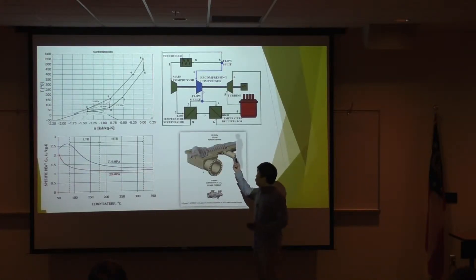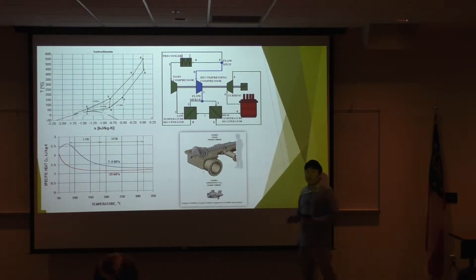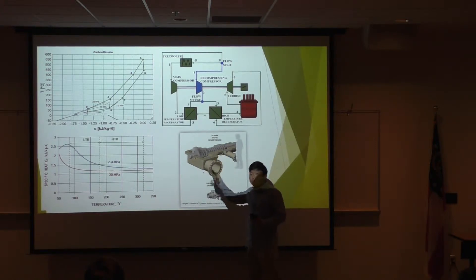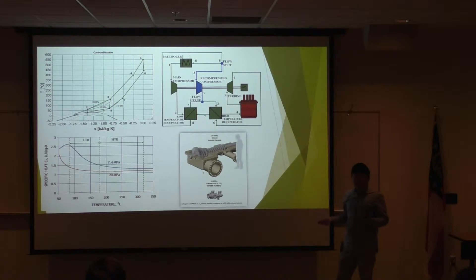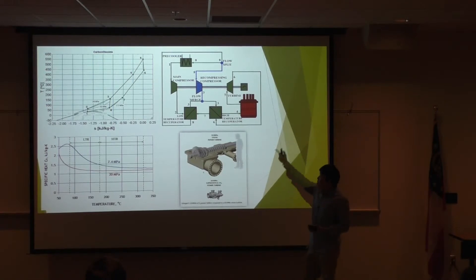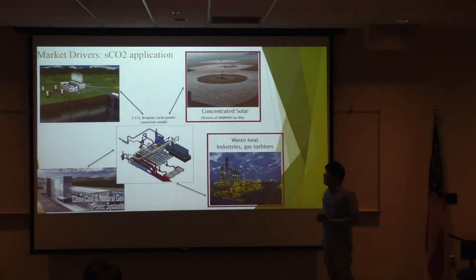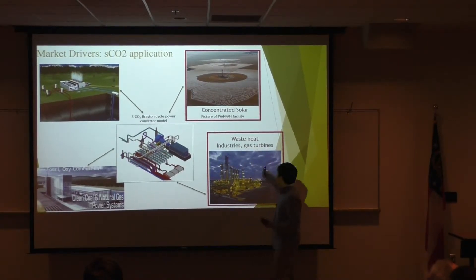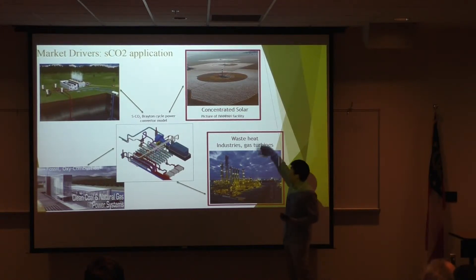This is one optimized supercritical cycle for a nuclear power plant application. For nuclear power plants, the maximum temperature goes up to 550 degrees C, and everything will be in the supercritical region. The steam Rankine cycle involves two-phase flow, which is really difficult to handle. But for this supercritical CO2 cycle, everything is in one phase, so we don't need to worry about two-phase flow. Applications for the supercritical CO2 cycle include geothermal, concentrated solar power, waste heat recovery, and nuclear power plants.